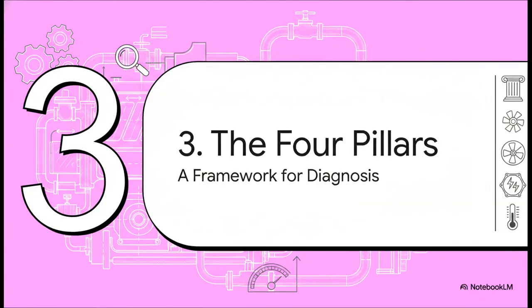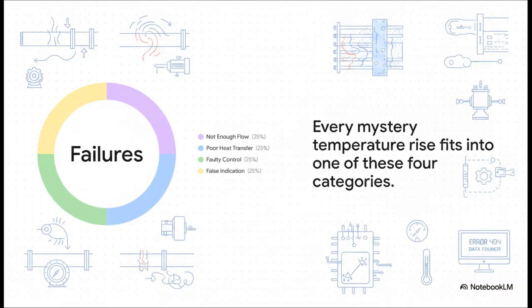Okay, once you've got that initial data, you need a way to think about the problem, a framework. The good news is, every single temperature rise can be traced back to one of 4 fundamental causes. We call these the 4 pillars of failure. Thinking this way keeps your troubleshooting logical. It stops you from chasing shadows. And here they are. Pillar 1, not enough flow. That's a volume problem. Pillar 2, poor heat transfer. That's an exchange problem. Pillar 3, faulty control. That's a logic problem. And Pillar 4, false indication. That's a data problem. Your job is to systematically figure out which of these 4 pillars is shaking.